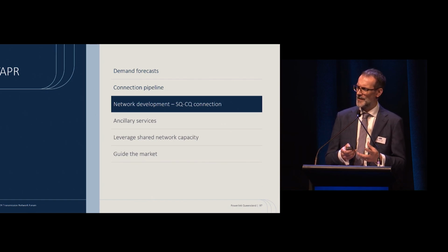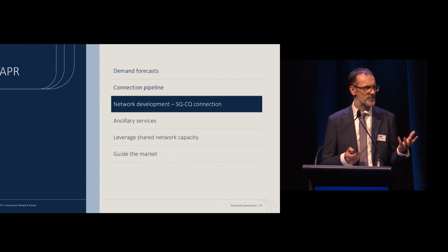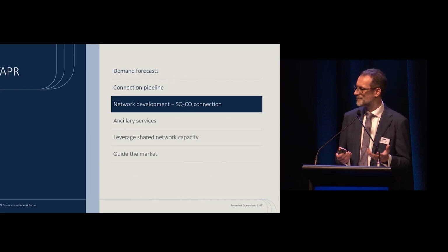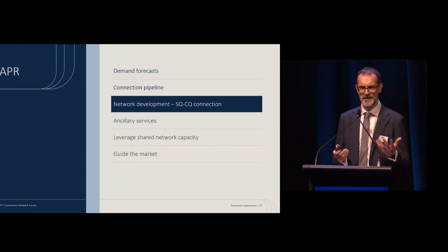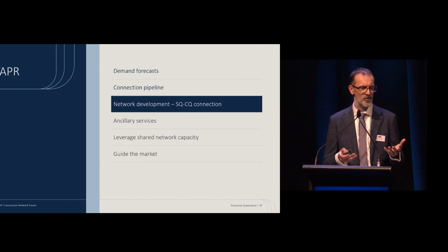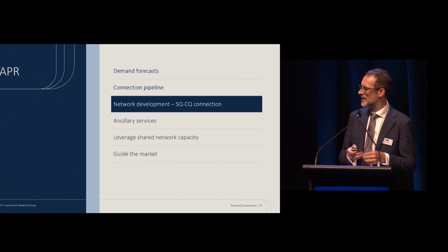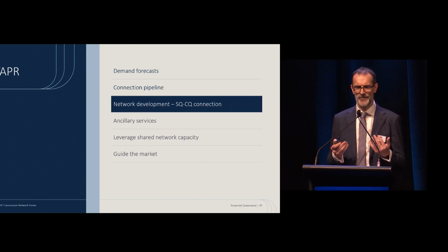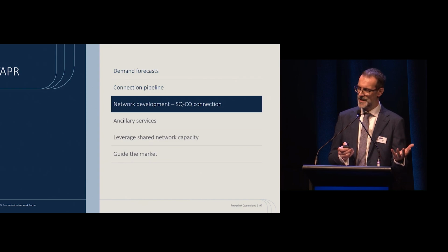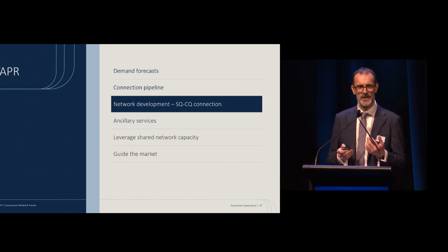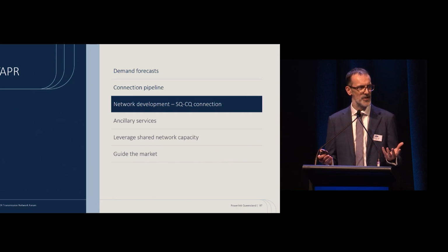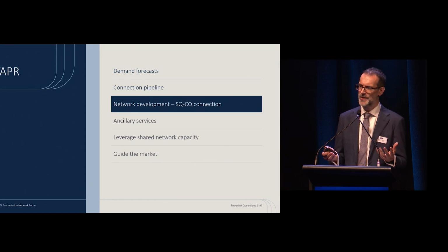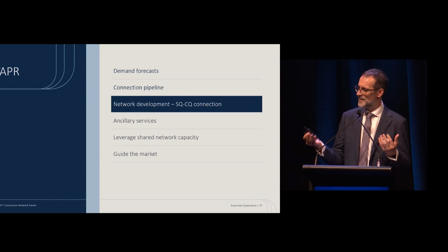Then there's the 500 kV backbone. Our modeling shows flows of about 16 gigawatts for a 12 gigawatt maximum demand network. You need those flows because you're meeting demand, but also charging up storage, whether pump hydro or batteries. So we're seeing far more flows on the network than before. We've got to have the network to take power from solar to the load and to storage, from wind and storage to the load at night, and from gas turbines to the load when it's not sunny and not windy. That's a far different proposition to a coal power station running at 90% capacity feeding the load. That's why we need the 500 kV backbone.